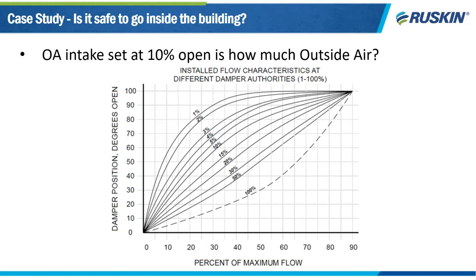The amount of air that comes in through a damper that's 10% open is a function of the damper's authority. Damper authority is what it's called, really, to have an effect on the amount of air that passes through the damper. A damper's authority changes as a function of the pressure drop across the damper.